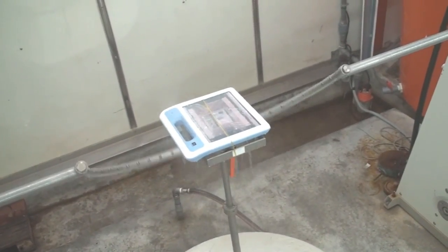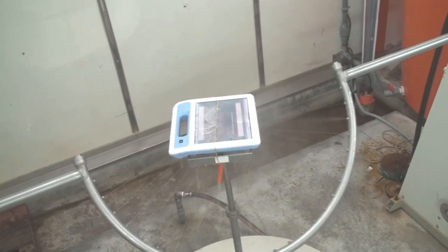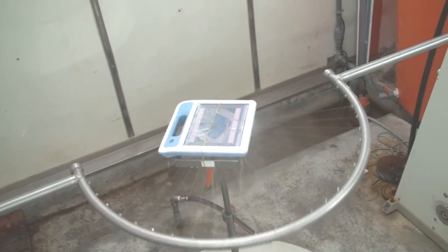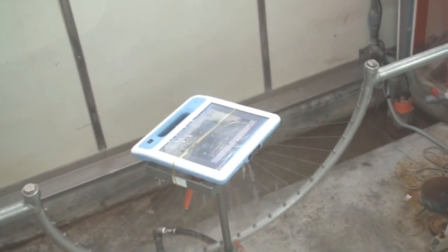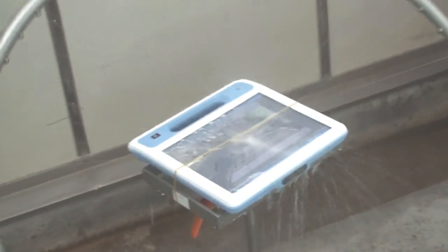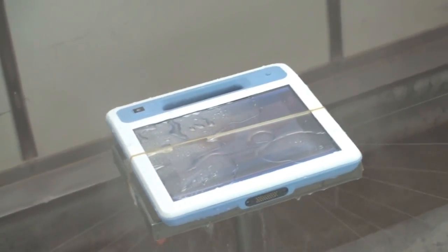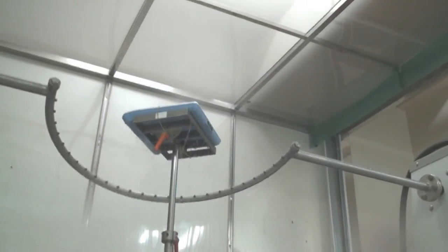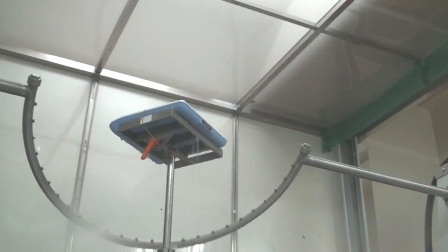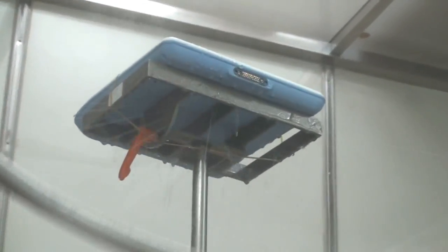In this test, the Mica 101 is turned on before the test begins. The water jets shoot toward the center from a 180 degree semicircle with a mean flow rate per jet of 0.07 liters per minute. The semicircle oscillates through nearly 360 degrees, 180 degrees on either side of vertical, subjecting the Mica 101 to water spray from every side.